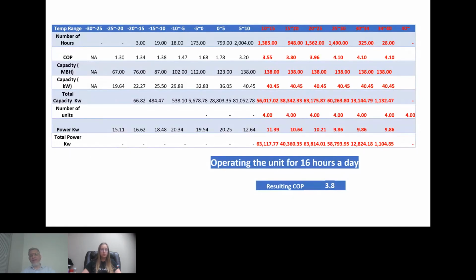We have flexibility, because we are not directly supplying hot water from the machine to the facility. We are charging a hot water tank that is supplying hot water to the building. So we have the liberty to choose when we charge it. If your temperature is good, you can run it at night time where you have good electric rates. If you have a lower temperature, like reaching minus 25, we do not want to run it at minus 25. We can run it at a temperature which is conducive to us and then charge the tank, so we don't run it at minus 25 centigrade.